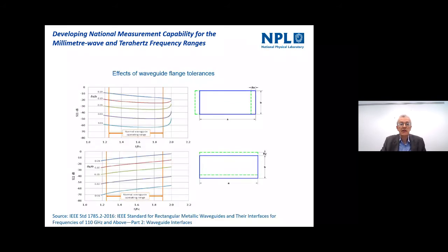So one can use that to predict performance from observed imperfections. When we go to the second standard, the part 2 standard, where we're looking at what we call flange or interface tolerances, there's similar plots that describe what happens when the waveguide is displaced laterally or vertically, and that's shown here on the right, where you can see a rectangle in green and one in blue, and they're not quite aligned in terms of their lateral position, and that will generate a reflection coefficient. So the reflection or return loss is shown on the left for different types of displacement. So once again, we can predict from observed lateral, vertical and rotational displacements, the electrical performance of these devices when they're used in measurement systems.